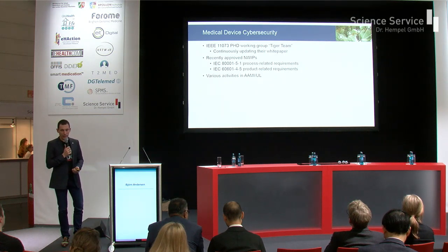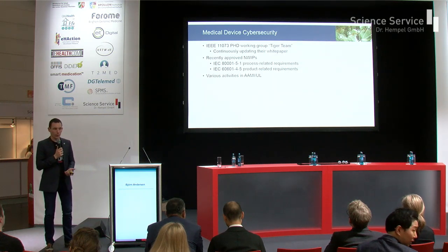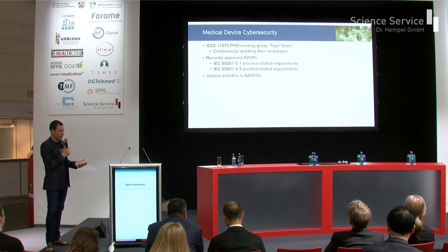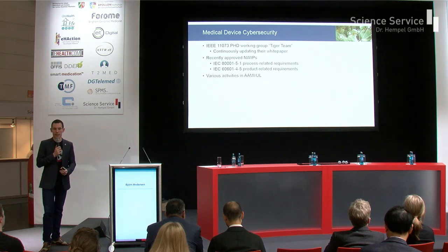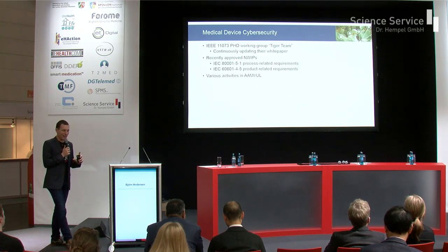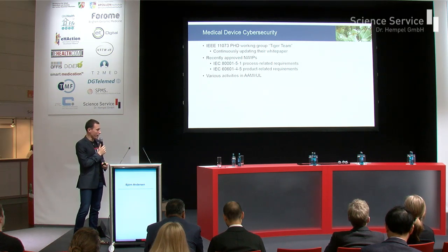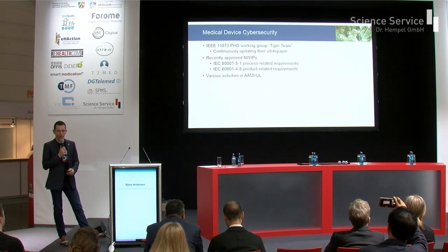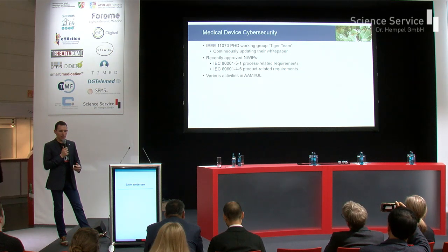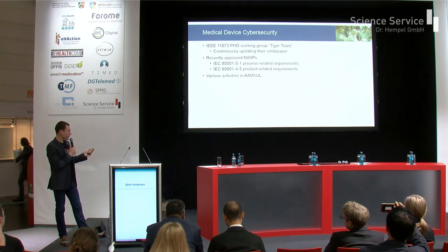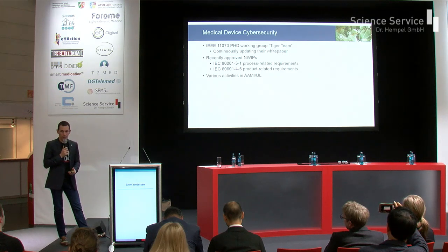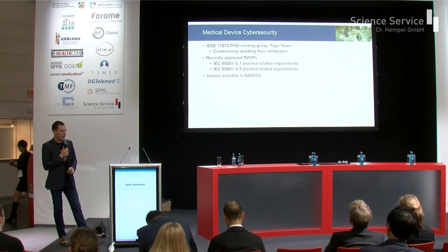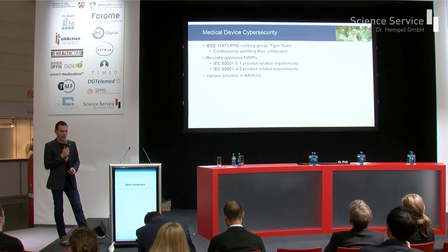And what's also happening, that's actually a German effort, is two new working item proposals on the international stage. One relates to process-related requirements for cybersecurity of medical devices, and the other to product-specific requirements. Those have just been approved a couple of months ago, and the development of the content is now underway. In parallel, there are a couple of activities in North America, namely the AAMI/UL series of standards that also relate to cybersecurity of medical devices.